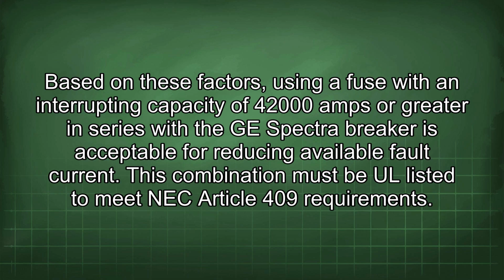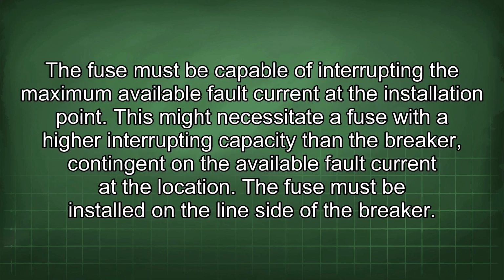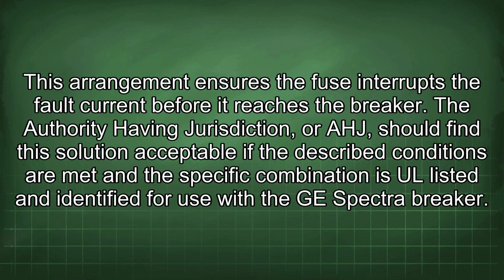Based on these factors, using a fuse with an interrupting capacity of 42,000 amps or greater in series with a GE Spectra breaker is acceptable for reducing available fault current. This combination must be UL listed to meet NEC Article 409 requirements. The fuse must be capable of interrupting the maximum available fault current at the installation point. This might necessitate a fuse with a higher interrupting capacity than the breaker, contingent on the available fault current at the location. A fuse must be installed on the line side of the breaker.